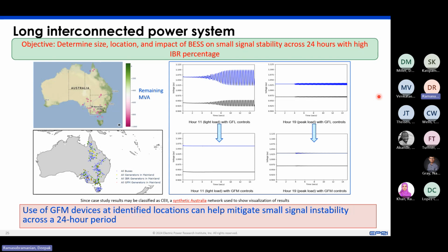The plant level control will still have a voltage control embedded in it, but that will be on a much slower time scale. You can't remove that voltage control on the plant level, because otherwise you might have fighting that occurs between the inverters within the plant. So you do have terminal voltage control at the inverter level that provides some level of response in the immediate time scale after a disturbance. And then you have a slower plant level voltage control that helps reset some of those controllers in a slow manner once you have ridden through the disturbance.